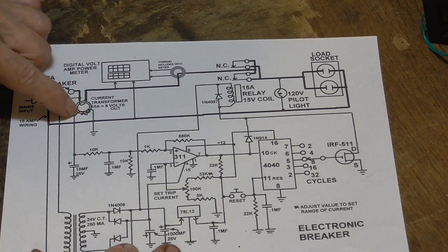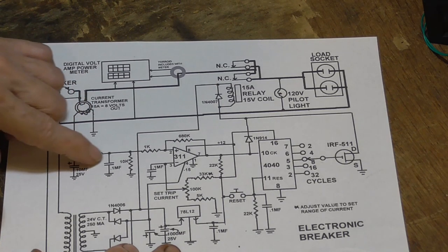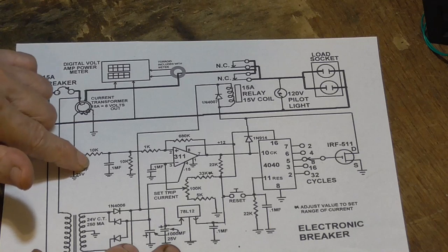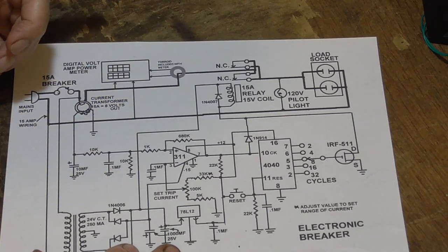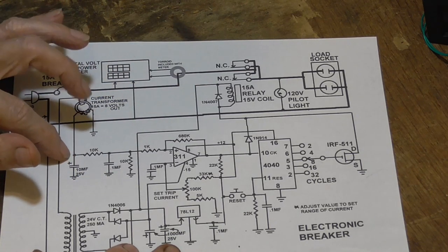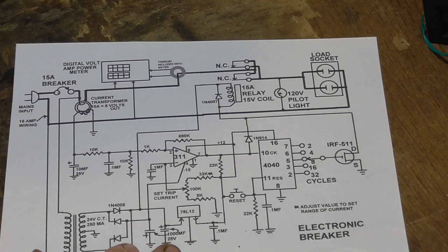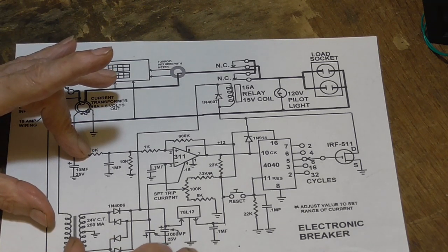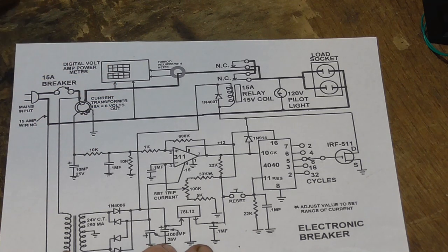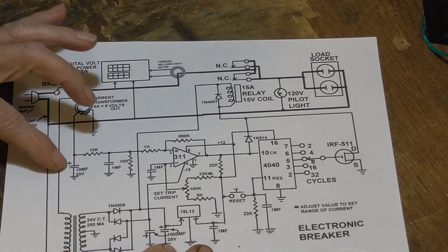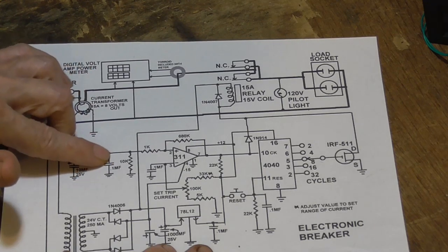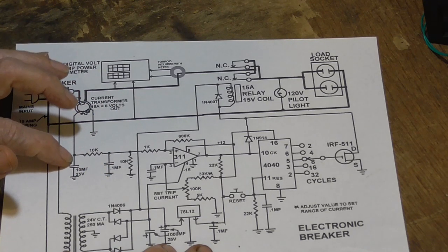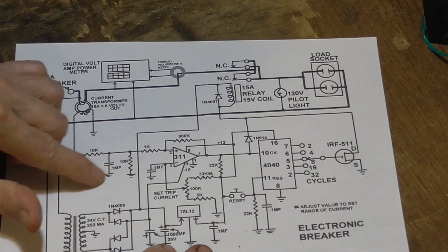Our current transformer output voltage is going to be fed through a filter. We need a filter because when something turns on, there'll be a spike current, usually well over any trip current we'd set. It might be a spike for half a cycle as much as 50 amps, even with capacitive input to the circuit. So we want a little filter here so spikes are completely eliminated, using a couple of capacitors and resistors.